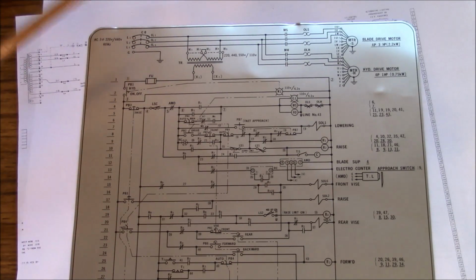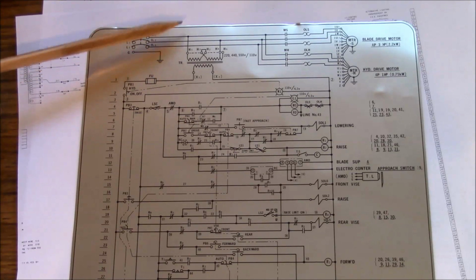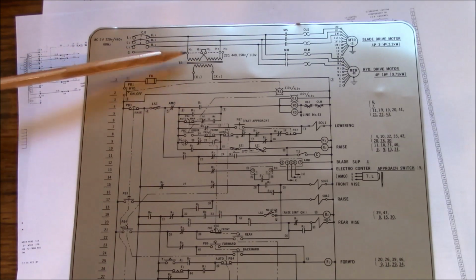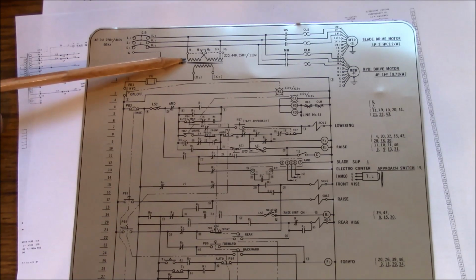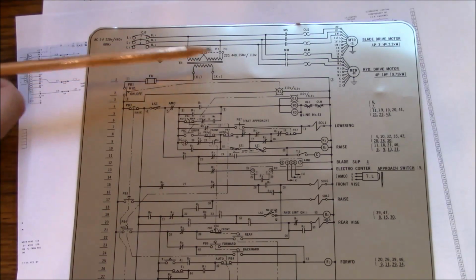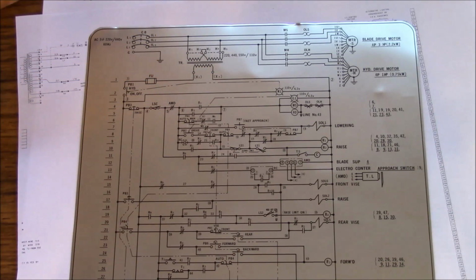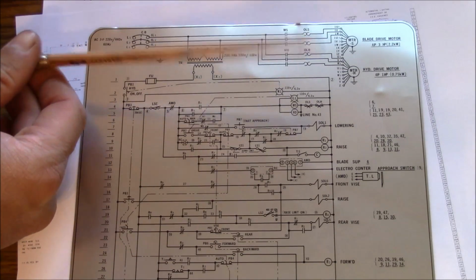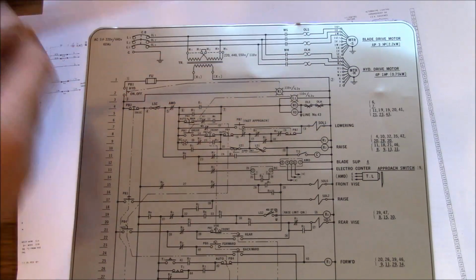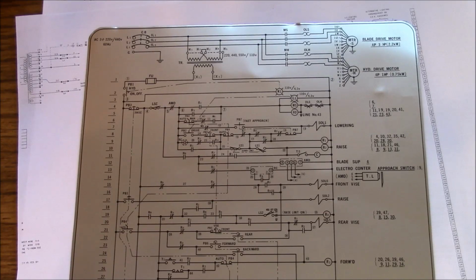So the first thing that happens is two of the phases, L1 and L2, go into a single phase transformer. X1 and X2 come out of the transformer and create the voltage for the logic. It looks like this is probably a 110 volt circuit for the logic in this machine, and that's pretty common for older machines. Nowadays everything pretty much runs on 24 volt DC, but in the old days, 110 volt AC was pretty common for this kind of application.